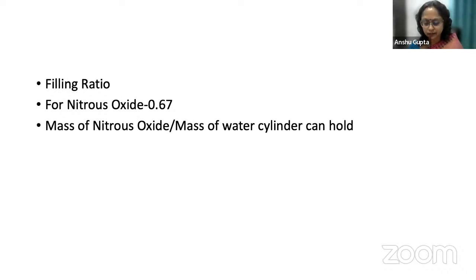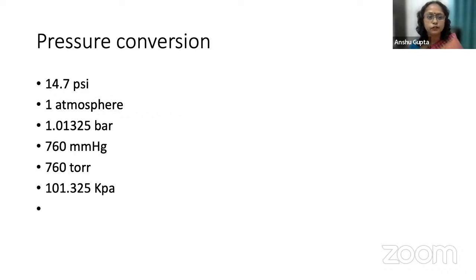So once the whole liquid is vaporized, only after that will the pressure drop down. So once the gauge is dropping, that means the cylinder is going to be empty soon. So we have to know the interconversion of the pressure units to read our gauges. Otherwise, it will be really difficult.